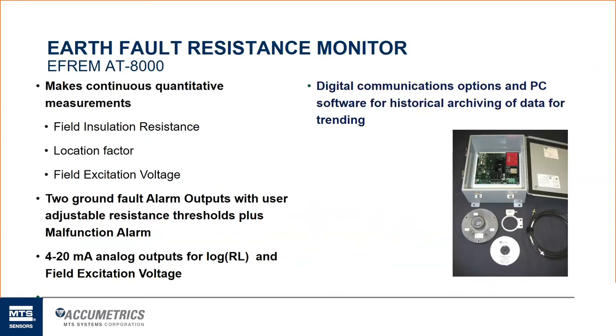We also offer digital communication options. Every system comes with its own PC software that allows you to have some historical archiving. You can trend the data through the software. It'll create a CSV file in Excel format and will allow you to trend that data. So if you, for instance, receive that warning alarm, a lot of times we'll have the customers go down to the receiver and plug right in with their laptop and start trending that information over a whole day so that we can take a look at that data and see it kind of moving in the right direction towards a ground fault or wrong direction, if that's how they would see it.